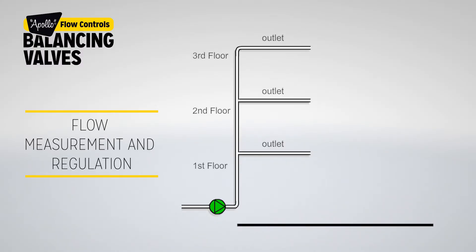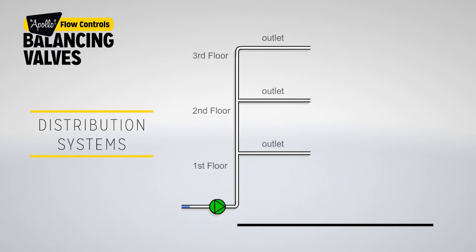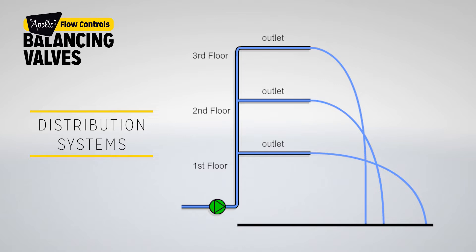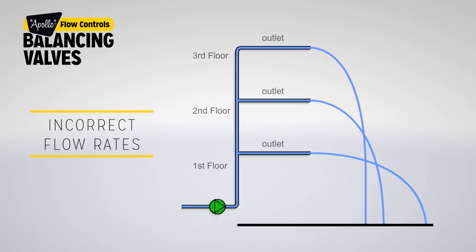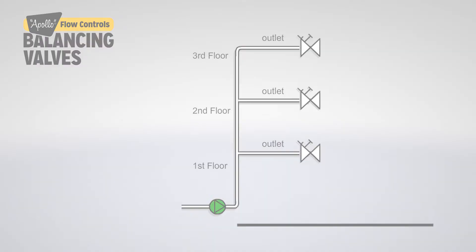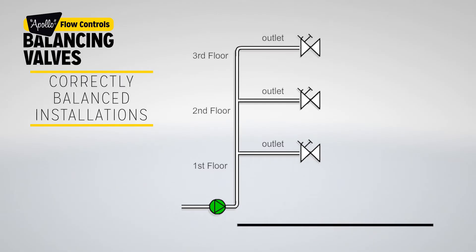The consideration for flow measurement and regulation arises from the fact that it is impossible to change pipe size or pipe configuration alone to achieve a balanced system. In most distribution systems, delivering the correct flow rate to each individual terminal can be a problem due to the different levels of resistance throughout the system. Incorrect flow rates in different zones of the building may lead to energy wastage or variable levels of occupier comfort.